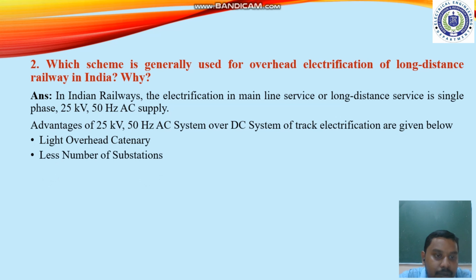Next is fewer substations. Since the voltage is 25 kV, the line current is less, and the line voltage drop, mainly due to line resistance, is correspondingly less, which improves the voltage regulation of the line. This allows for larger spacing, about 50 to 80 kilometers, between substations.